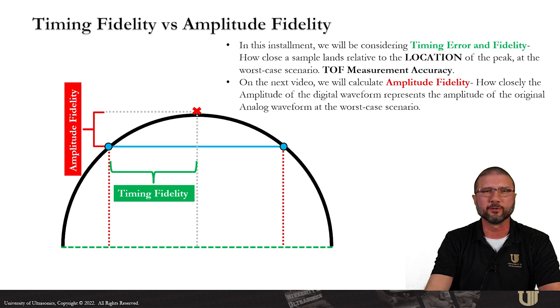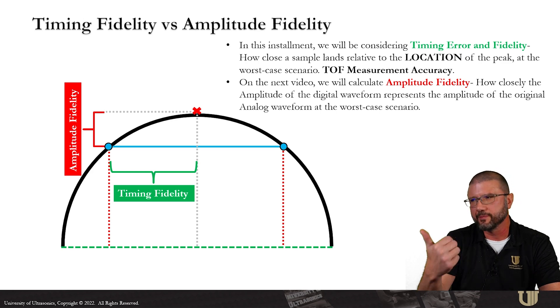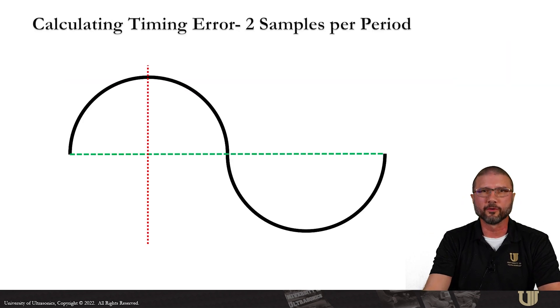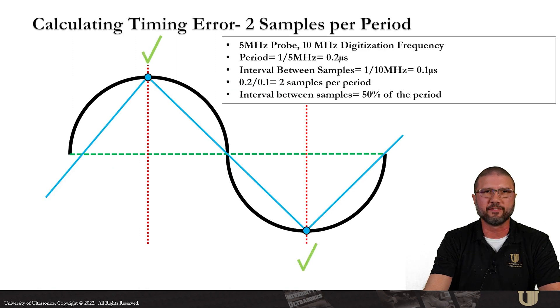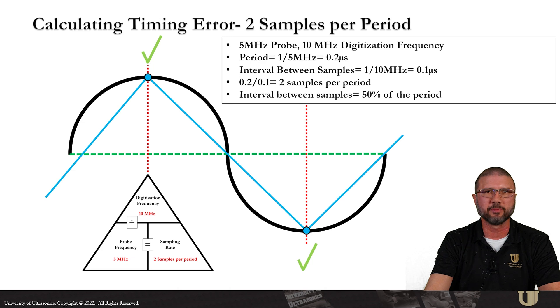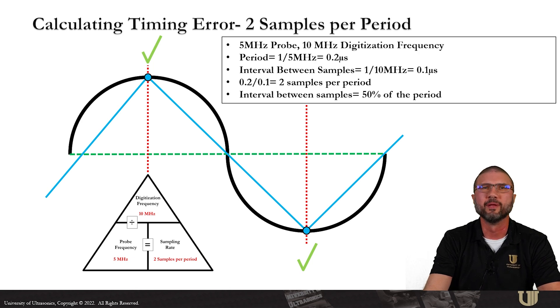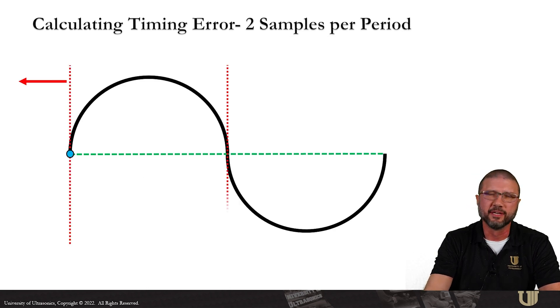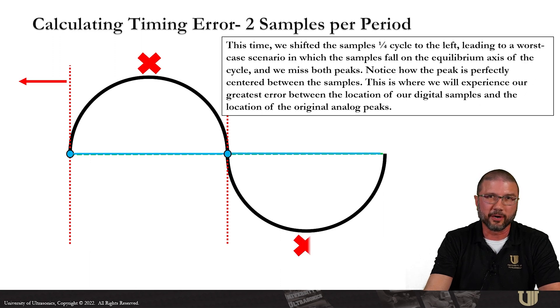Worst case scenario for accuracy always occurs when a peak is centered between two consecutive samples. For the first scenario, I'm considering a 5 megahertz probe and a 10 megahertz digitization frequency, which would result in two samples per period spaced equally down the length of the cycle — we can also call this the Nyquist sampling limit. Best case scenario, we get a sample on both the positive and negative peaks, meaning amplitude and timing fidelity would have been preserved. The problem with Nyquist is those samples could occur anywhere and there's no guarantee we're going to find the peak.